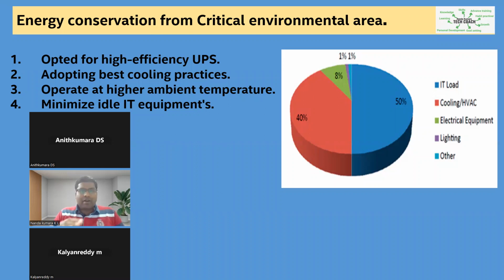Similarly, even our data centers and labs have some energy conservation options available. You are able to see this pie chart. In any of the labs or data centers, you can see 50% of the power consumption is from IT equipment. Then 40% is cooling or HVAC equipment. 8% is consumption from electrical equipment, including transformers, UPS, cable losses, whatever may be, etc. And 1% lighting, and 1% other losses.